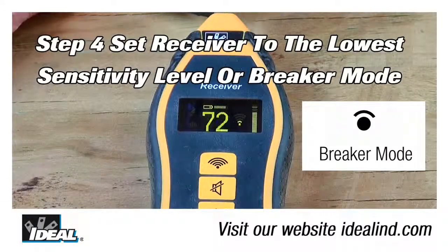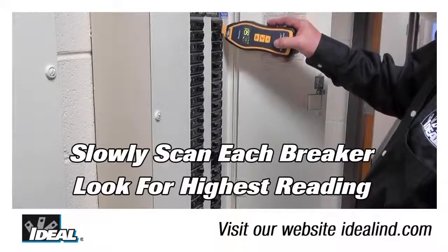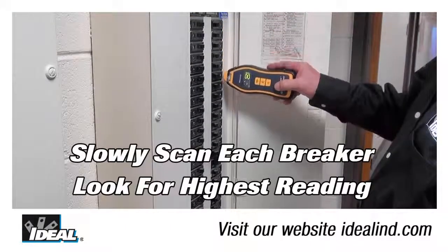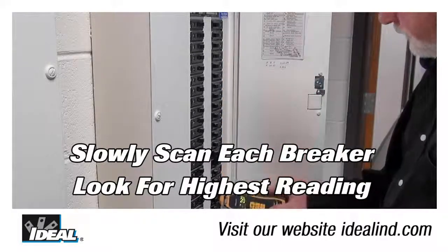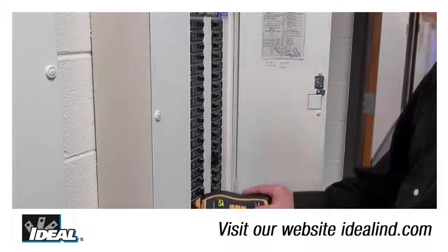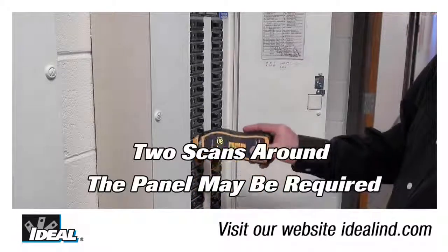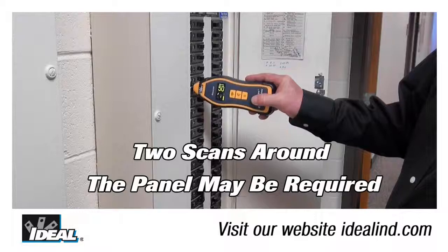Step 4 is to set the sensitivity to the lowest level or breaker mode. Open the correct electrical panel door and properly identify the breaker by simply slowly scanning each of the breakers with the receiving unit while looking for the breaker with the highest reading. It may take a couple of passes to identify the breaker with the highest signal.